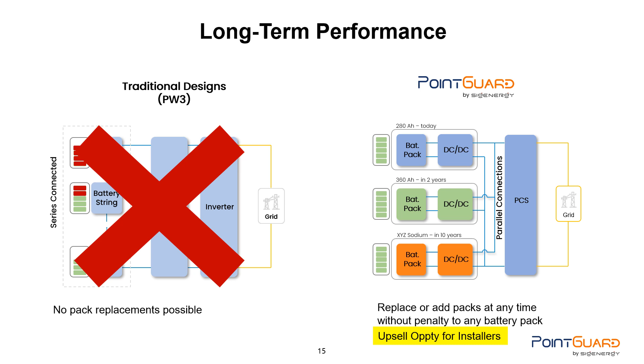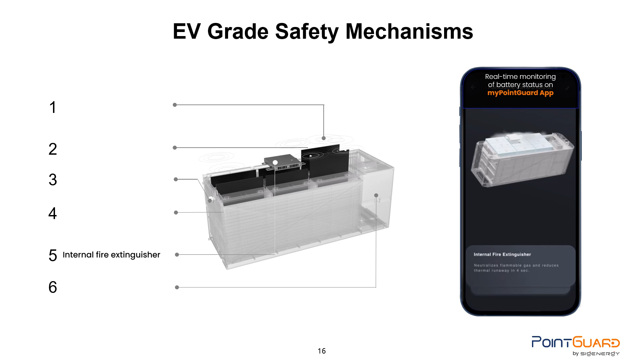PointGuard Energy is totally unique in having integrated EV-grade safety mechanisms into our battery packs. We have 6 major safety mechanisms in each pack, which I will not discuss in detail here. However, I would like to call out one single mechanism, our internal fire extinguisher. This is a heat-activated device that releases a gas that neutralizes hot flammable gases coming from a lithium-ion fire. We are actually extinguishing a lithium fire should a thermal event occur in one of our battery packs.